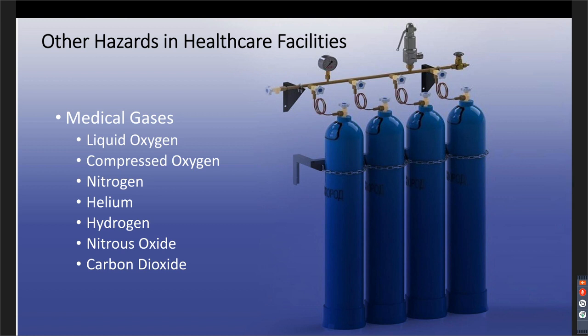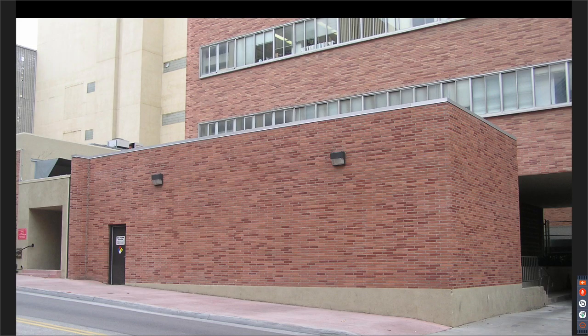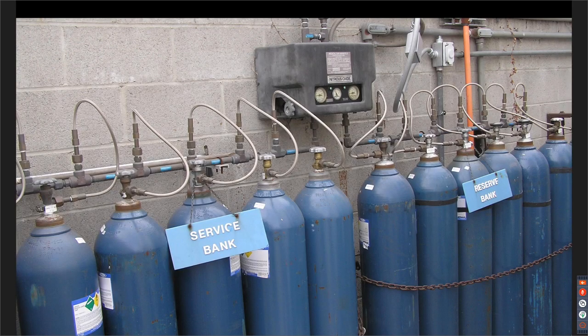Sometimes these liquid oxygen or bulk oxygen systems need special consideration. So in this particular example, this building is a bulk oxygen facility building, but the windows that you see directly above it are in a school of medicine, which would put the bulk oxygen too close to the opening. So getting creative with the design was required at this particular facility. Of course, the requirements for medical gases apply to other than just oxygen. So in this case, we're using nitrous oxide.